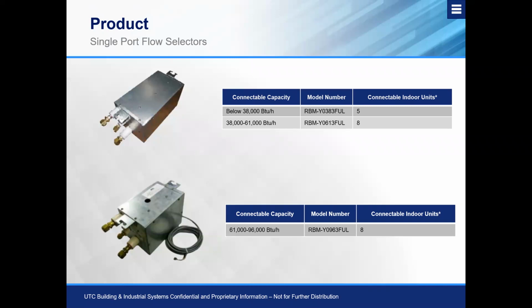capacity. Okay. And as I noted before, if you look on the bottom selector box here, we see this little whip that comes supplied with the flow selector. All this is a communication plug that plugs into the indoor unit for communication so that these two can work in unison. Same thing goes with power, so that we can use power from the indoor unit out of this box, which is one of the advantages of using this box. And of course, as I stated before, the other advantage with this box is that it does not require Ethernet. It's compact, it's power and communication, it's corresponding indoor unit.